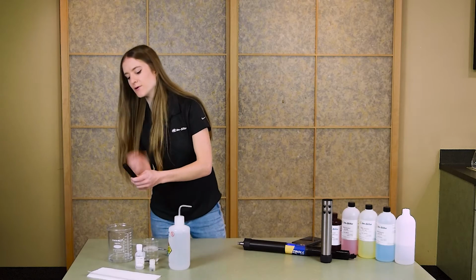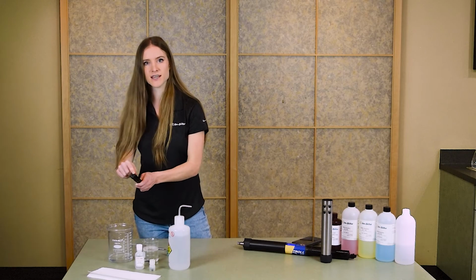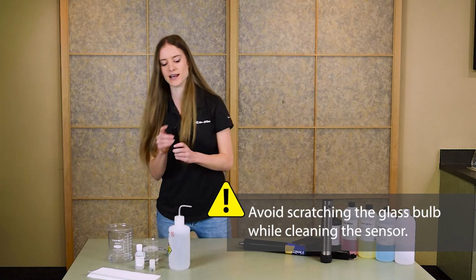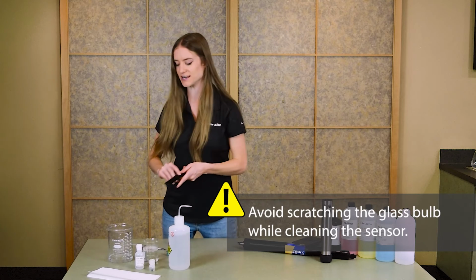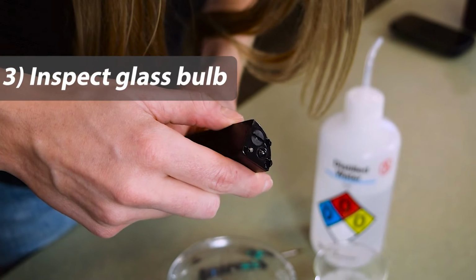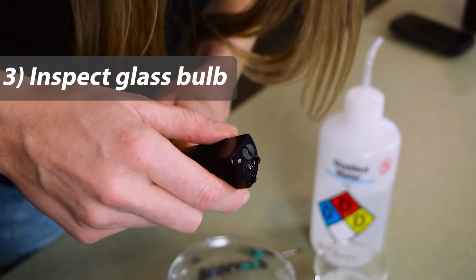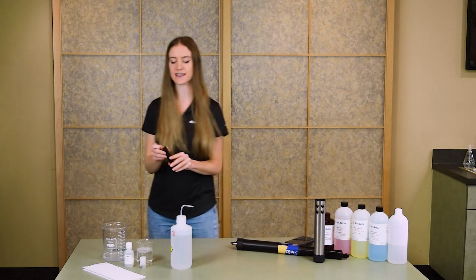You'll also want to avoid touching the glass bulb too directly with your fingers, paper towels, or anything abrasive so that you don't scratch or damage it. Inspect the glass bulb for any scratches or tears. We'll replace the filling solution inside the sensor now.